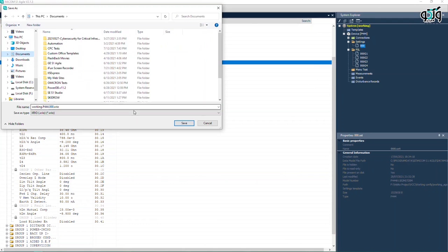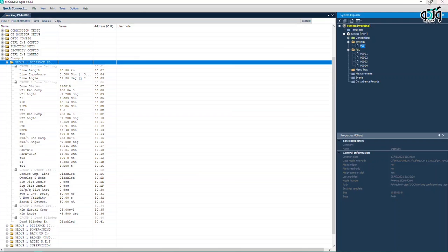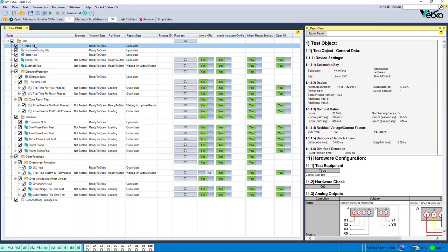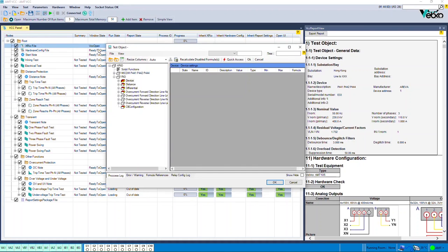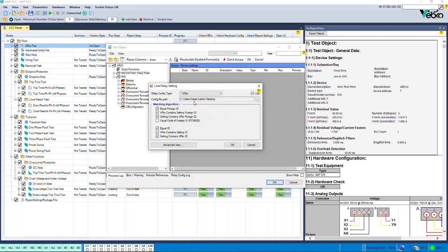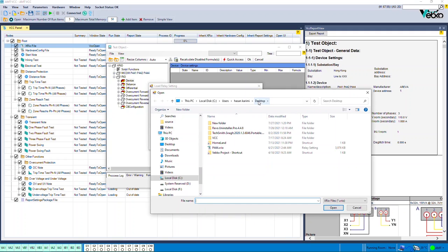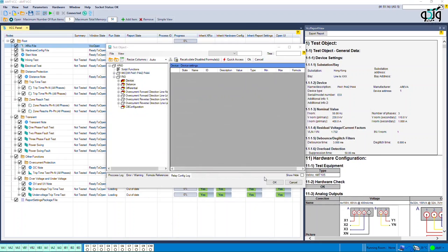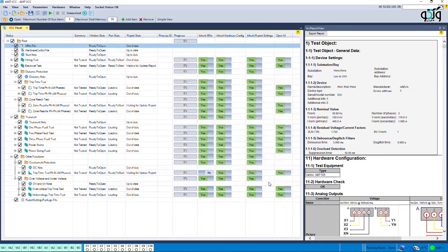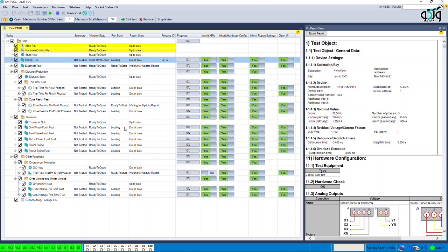In the next step, we re-enter the AMT VCC room and first load the template related to the P444 relay. Now we prepare different function tests using the XRIO file that we took from the relay in the previous step. By running the test, you can control the test of different functions step by step.